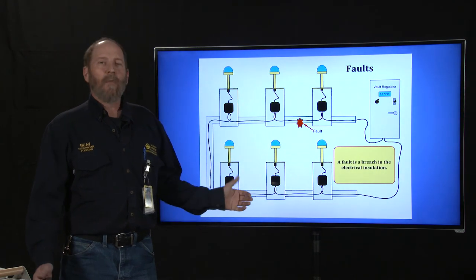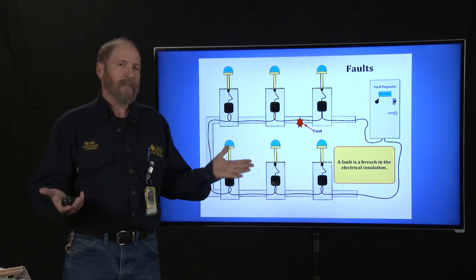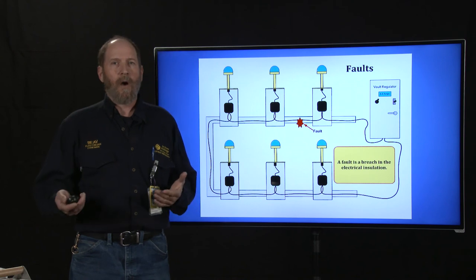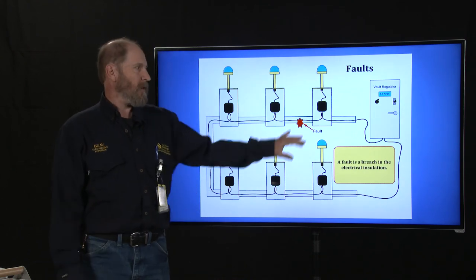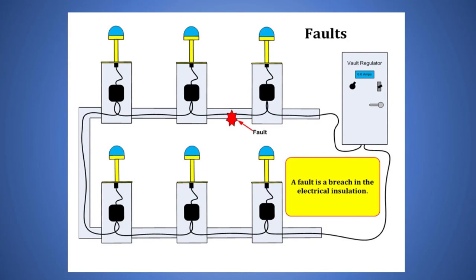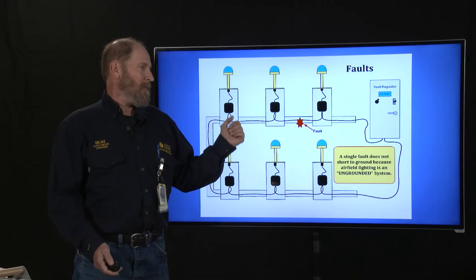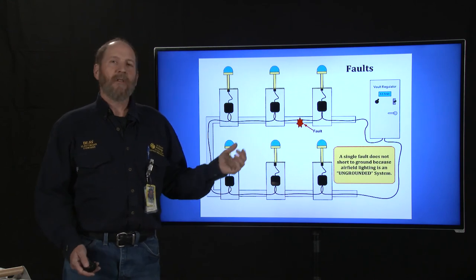So the next thing we're going to talk about is faults. Now a fault is just a break in the insulation somehow. It could be in the wires, it could be in the transformers, it could be anywhere. Now a single fault doesn't go anywhere. It just sits there. And the reason it does that is because airfield lighting is an ungrounded system.